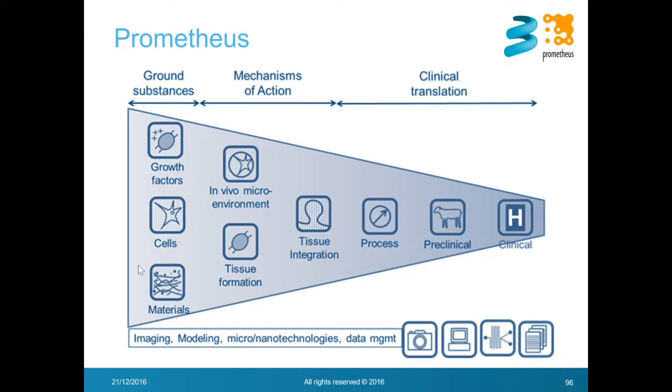But on the other hand, they will also want to issue more guidelines so that this all becomes standardized and streamlined. In the spring next year, there will be the V&V40 guidelines that come out. Those are verification and validation guidelines made by the ASME and the FDA together. ASME has these standards for other engineering fields, but now for medical devices there will also be the V&V standard, which tells you what to do to make sure that your model is verified and validated. I think that's also something interesting for us to keep an eye on.